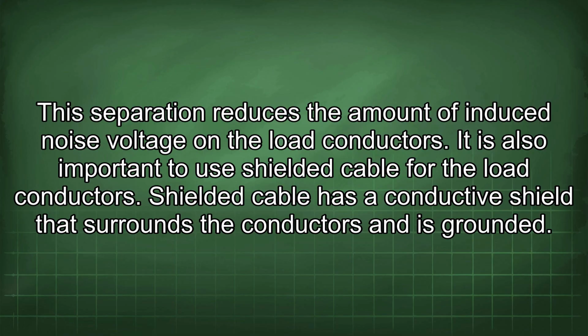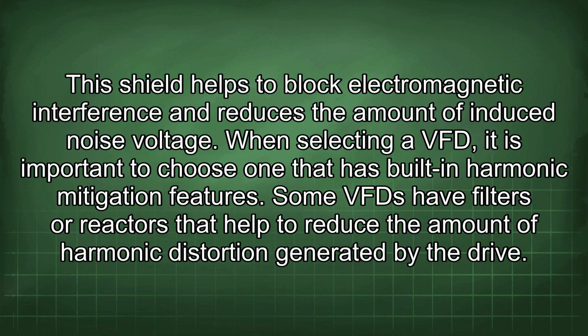It is also important to use shielded cable for the load conductors. Shielded cable has a conductive shield that surrounds the conductors and is grounded. The shield helps to block electromagnetic interference and reduces the amount of induced noise voltage.